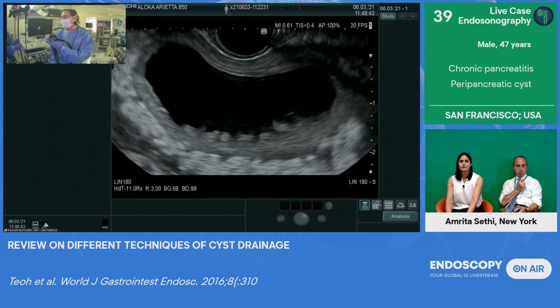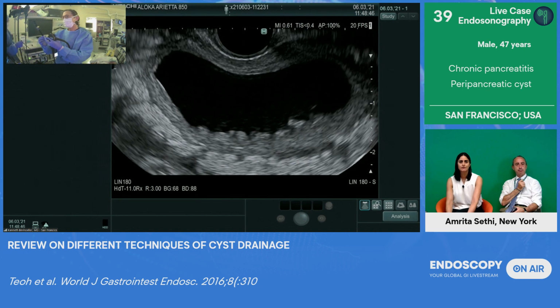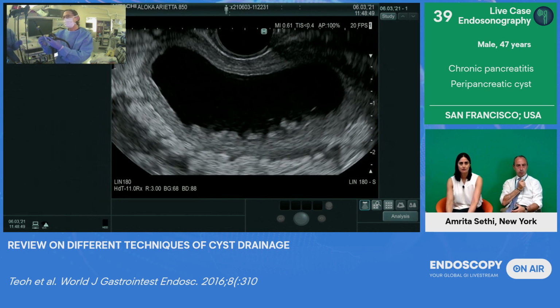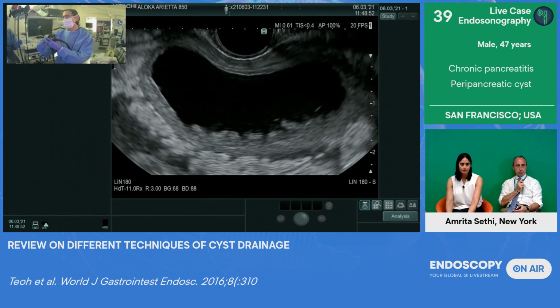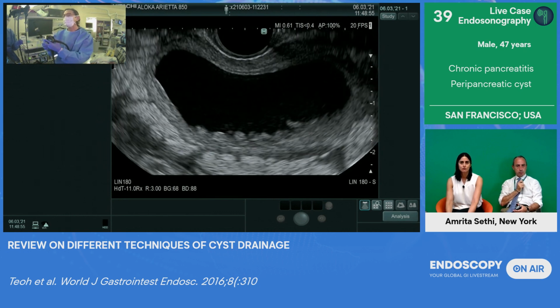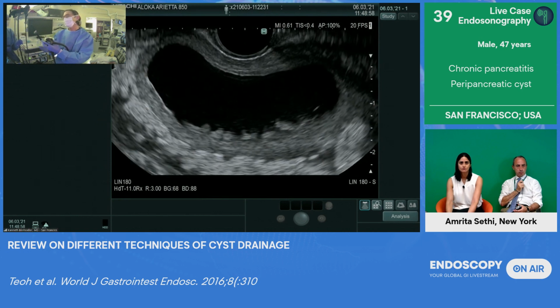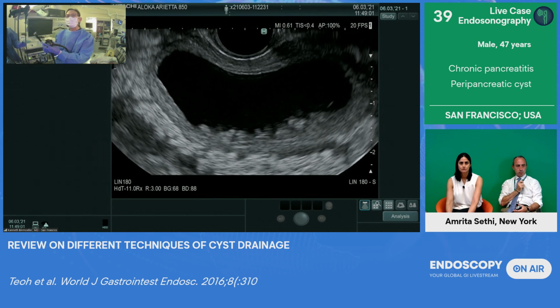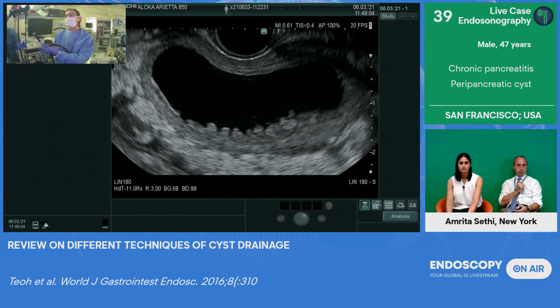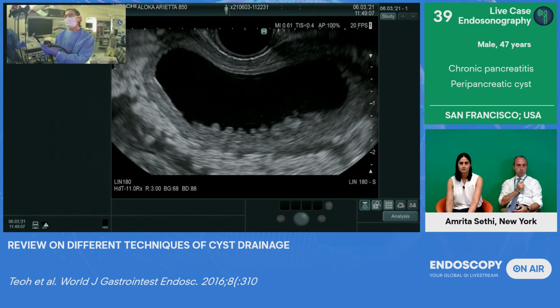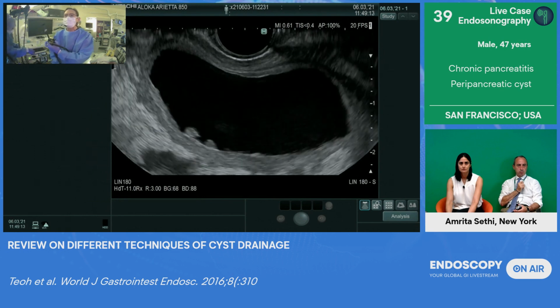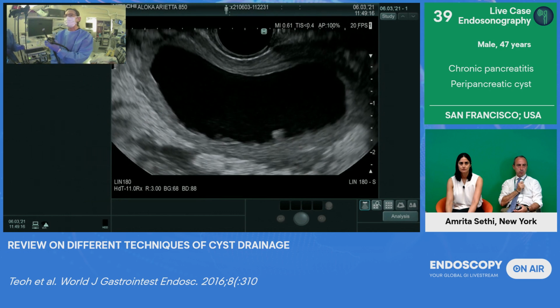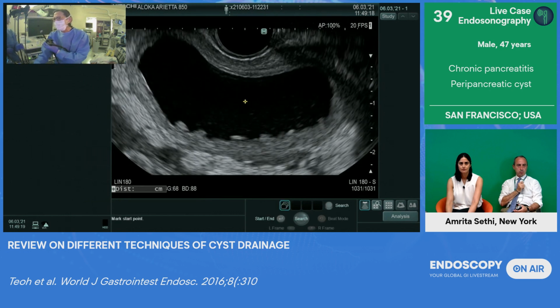This next part, the numbers you were referring to were the diameter. I believe now there's also two saddle lengths available, a 10 and a 15. How do you choose which one to use? That's correct. So, generally, I rarely use the 15 saddle length because if it's already that separate from the wall, I just have some other concerns that need to be addressed, but usually the 10 millimeter saddle length is sufficient. Now, in this case, you can certainly measure out the distance here if you're not sure. So you'll see this is only 4 millimeters.